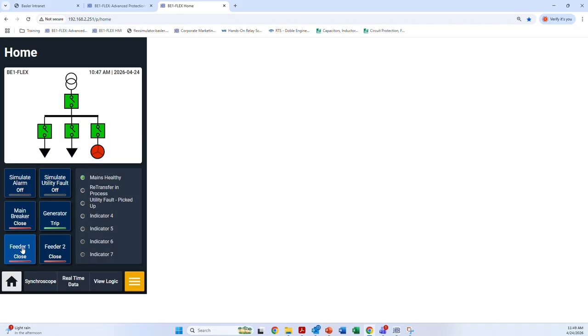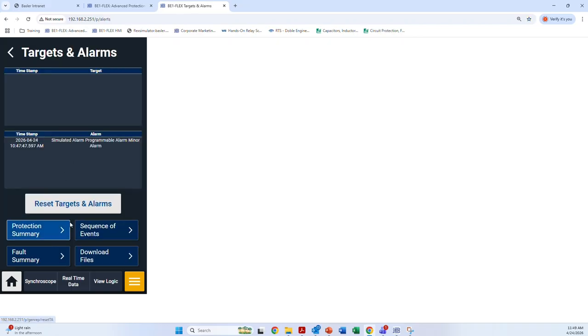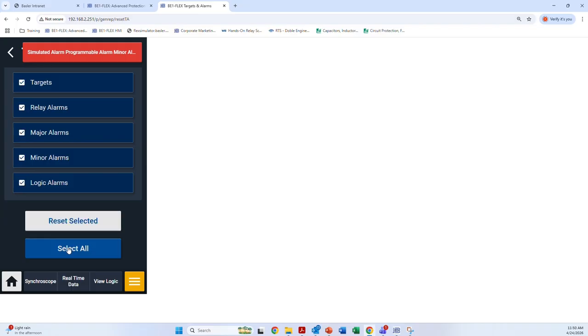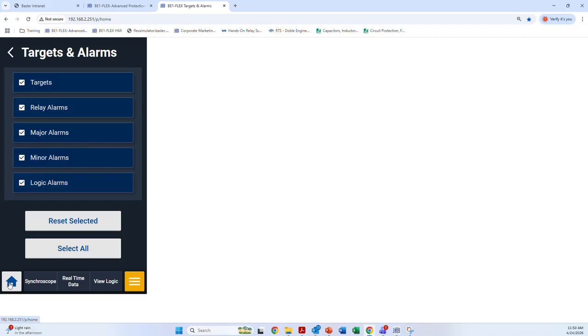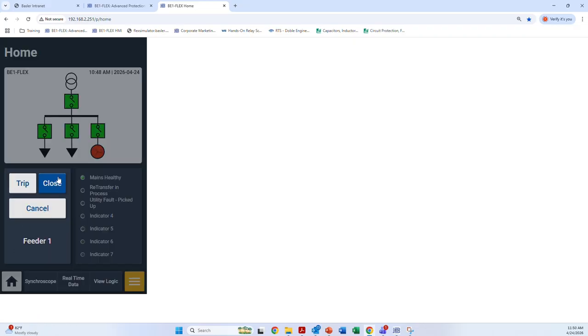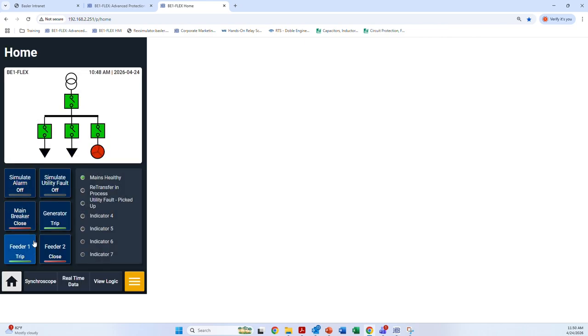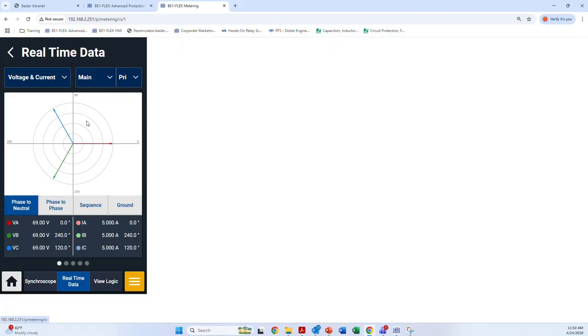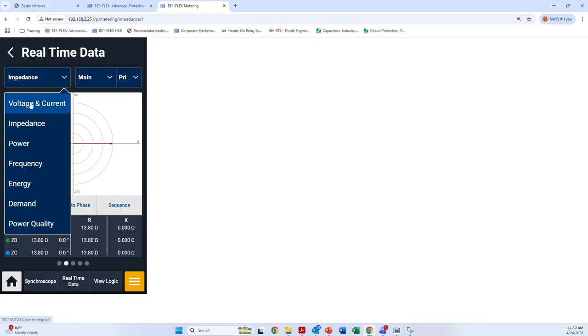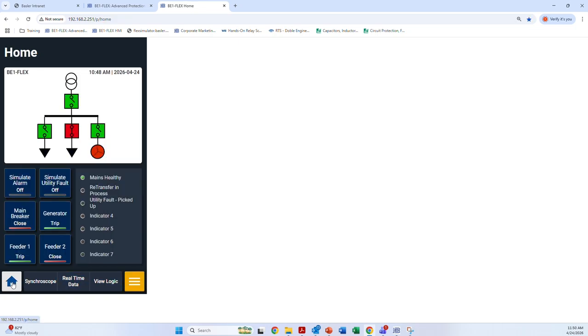You can use those to make a particular control action. I'm simulating alarm so you can see the control banner. You can then select that red banner to navigate and reset the alarms or targets. I can also close the breaker and see the status of that breaker I am controlling. You can look at real-time data, voltage and current via the phasors, phase to neutral, phase to phase, or sequence or ground. Select the source, primary or secondary, and what you want to read, whether it's impedance, voltage, or current. Click on the home screen, and you're back to the home screen.